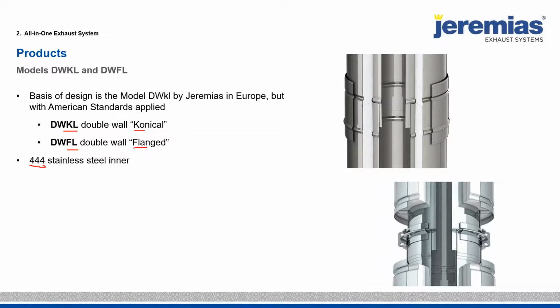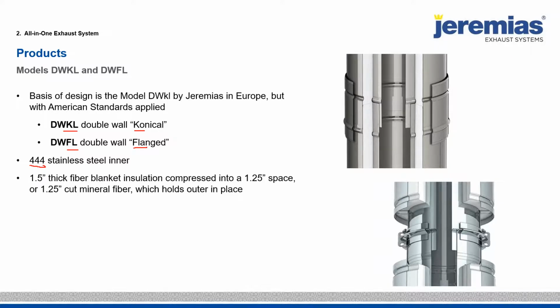This is a super ferritic steel, very similar to AL294C. You may have that in some of your specs. It's actually approved as an equal, but it does not have as much chromium, which means we can have higher temperatures safely with the 444 stainless steel. I'd recommend every engineer to Google that steel to see what it is and the uses of it. It's very good for corrosion and sulfuric acid situations.